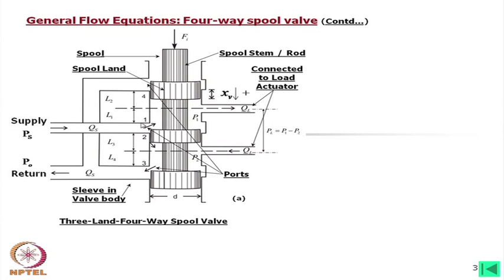The ports are also numbered 1, 2, 3, 4. On the load side we have flow QL entering and the same flow QL returning, since this is an incompressible fluid. However, the supply flow and load flow may not be equal due to leakage, and this leakage is essential to consider in valve analysis.